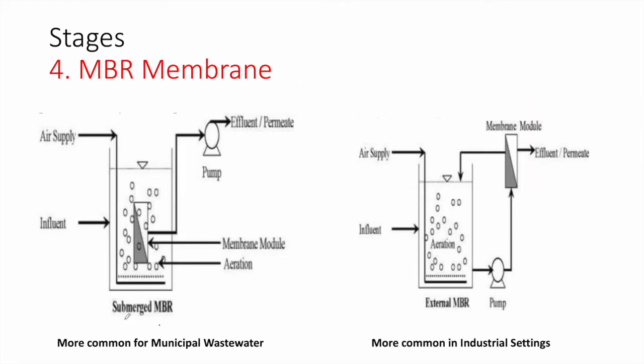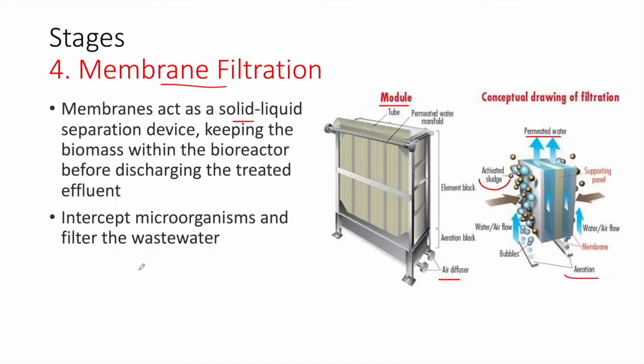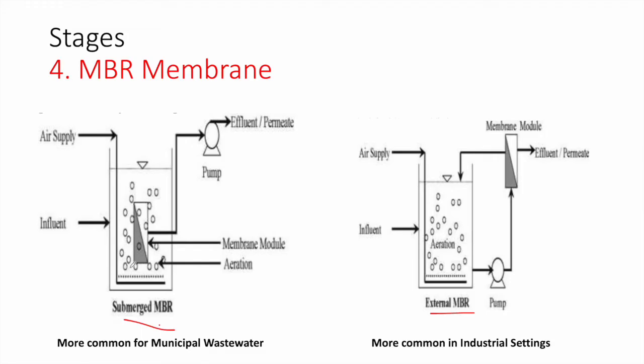MBR modules can be submerged or external. The submerged modules are placed within the wastewater — just imagine this module placed within a tank with air diffusing and water being cleaned through these modules. This is more common for municipal wastewater, such as domestic sewage. External MBRs are usually tubular — we have tubes filled with MBR sheets or filters that are outside the aeration tank — and these are more common in industrial settings.